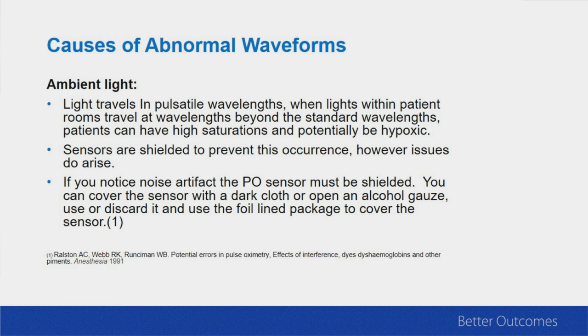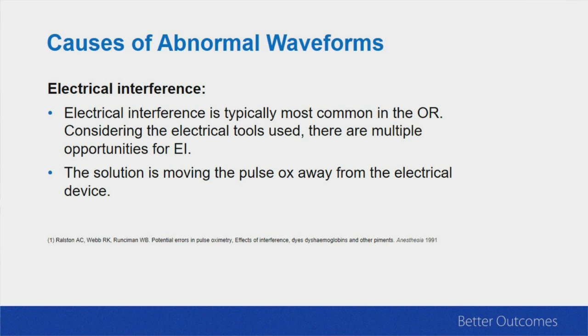Now, another thing that causes that noise artifact, that real choppy signal, is electrical interference, and this is common in the OR. Consider the amount of electrical tools and devices that are in an OR. Again, all of those will be shielded to try to protect against this issue, but you have multiple opportunities for electrical interference. So your answer to correcting this problem is you need to try to move the pulse ox sensor as far away from the electrical interference as you can. And in the OR, there's so many devices. If you happen to get interference whenever a doctor is running a particular tool, try to get away from that tool as your answer to this, or just understand your data is going to be wrong during that period of time, and when he stops the tool, things can return back to normal.